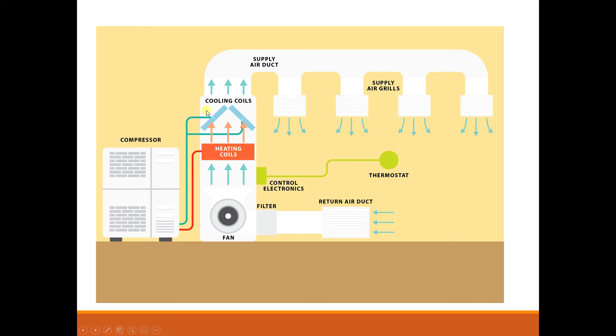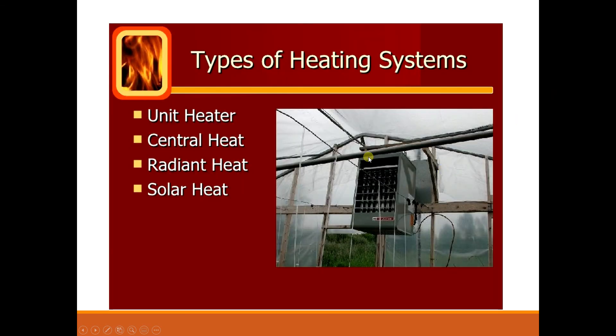In a centralized air conditioning unit, which was discussed previously, we were using a cooling coil only. Here we are also using a heating coil - in winter we need heating, not cooling, so the cooling circuit is switched off and the heating circuit is switched on. The return air from the duct is sensed by the thermostat and accordingly heating is adjusted in the heating coil so that we get hot air supplied to all buildings.